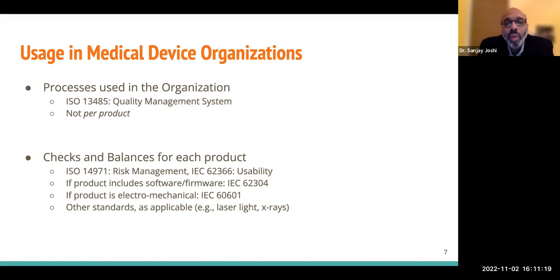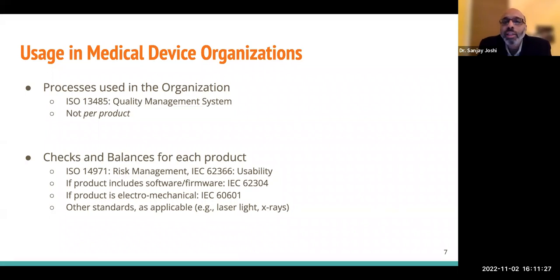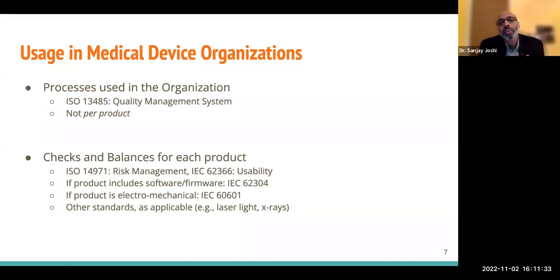Depending on what your device has — for example if it has a laser light or X-rays — there are different standards to comply with, and that changes device by device. That is why certification to those standards is by device, not by organization.